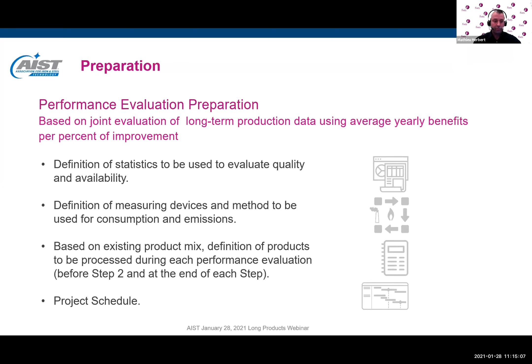During this preparation step, we will also define the project schedule, because you will see that some of the steps have to be synchronized with furnace outage, maintenance outage. Step 2 is a step that is synchronized with the first maintenance outage after the preparation is over. It's a 5-week site mission to perform the baseline performance evaluation and to apply the immediate improvement, quick win savings.